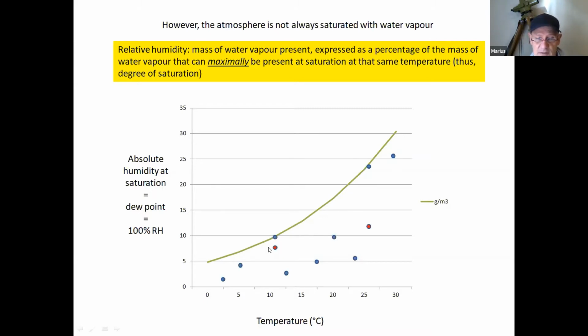The red circle just below it is not at 100% humidity because at 10 degrees Celsius, this has about 7.5 grams of moisture per cubic meter of air. Maximally, what the air can hold at saturation is the 10 grams. So 7.5 out of 10 gives me a 75% degree of saturation, or 75% relative humidity.